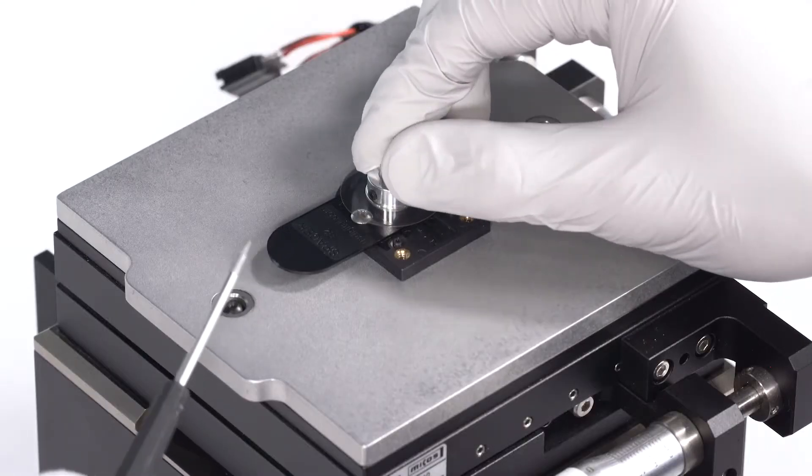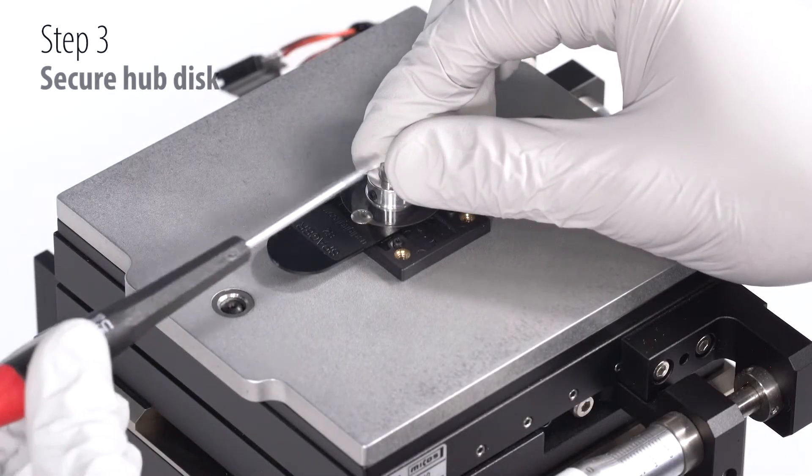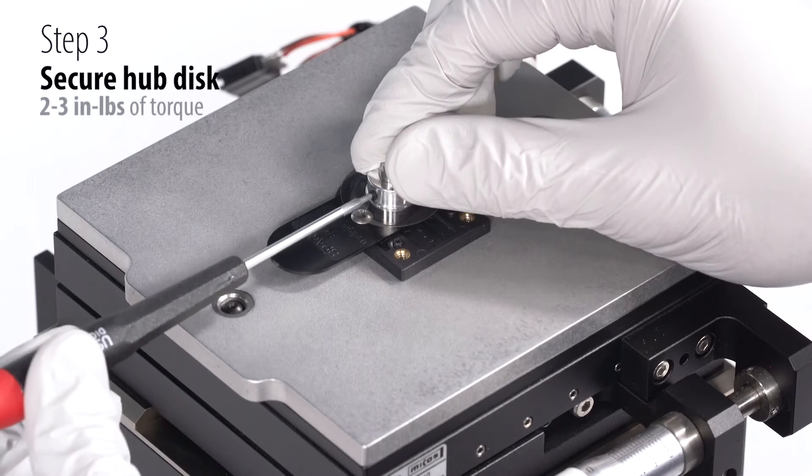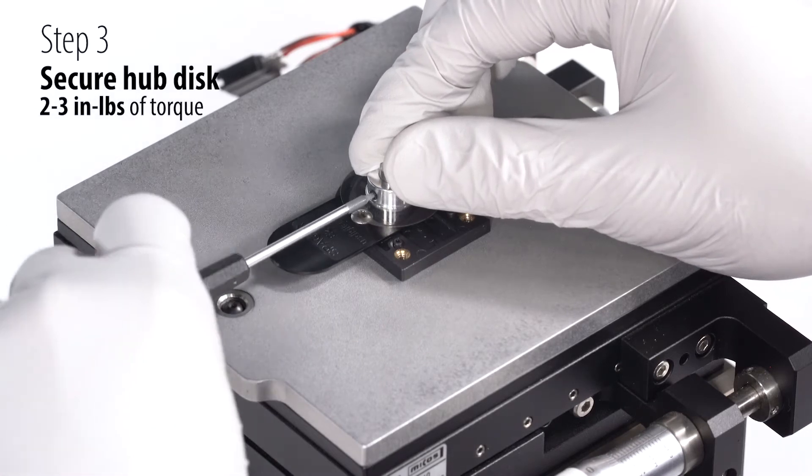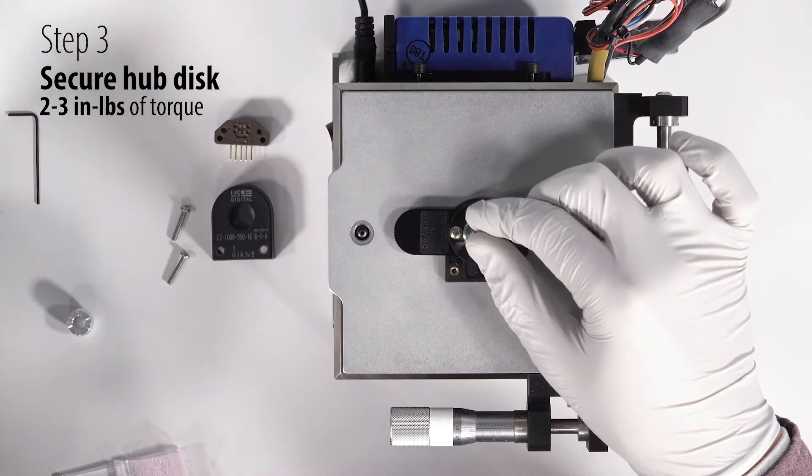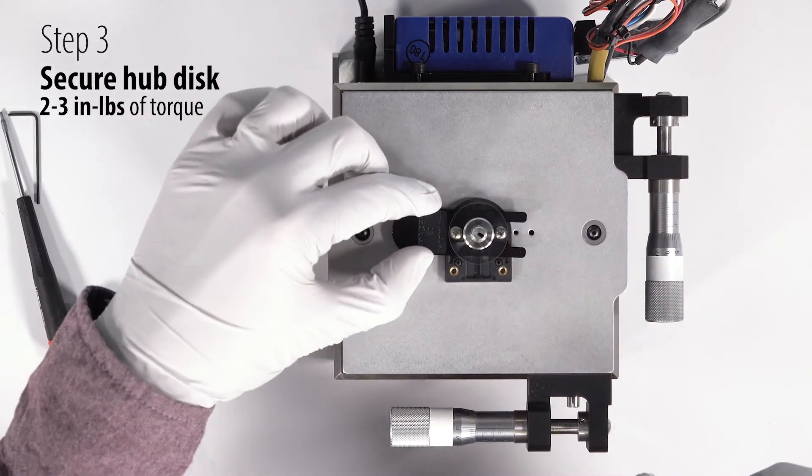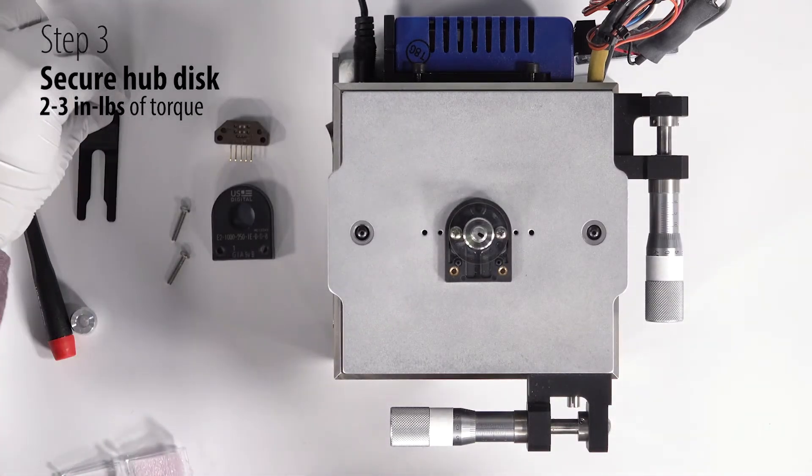For step three, we're going to tighten this set screw to two to three inch pounds while maintaining downward pressure on the hub disk assembly. Then remove the spacer tool for use with later installations.